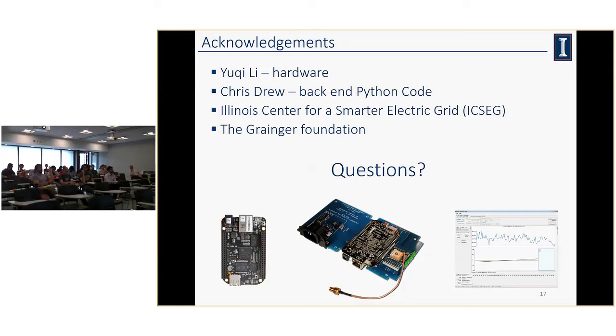Right. Sure. Have you been able to assess the accuracy of the measurements? So frequency is good. We're within like 5 millihertz at 60 hertz with a pretty good, clean, calibrated sine wave. The voltage measurements I'm still working on. For example, with a pretty good calibrated source at 120 volts RMS, we're at 120.03 volts or something along those lines. And that's not a particularly detailed calibration at this point. I'm still in the lab measurement stage. But with 14 bits, we're on the order of our competitors, and we should be able to meet the spec requirements.